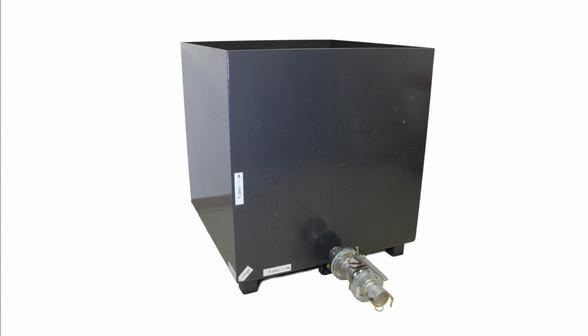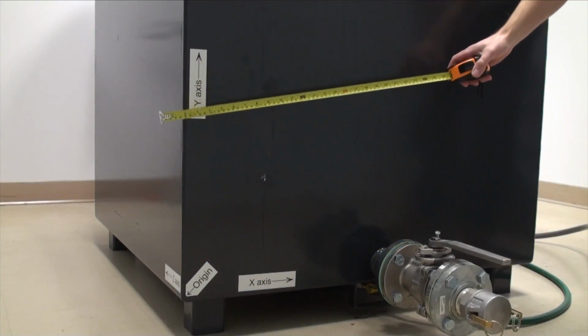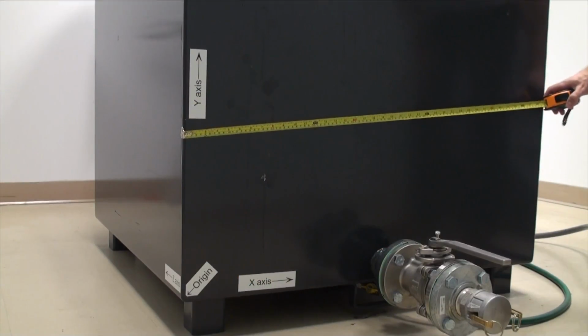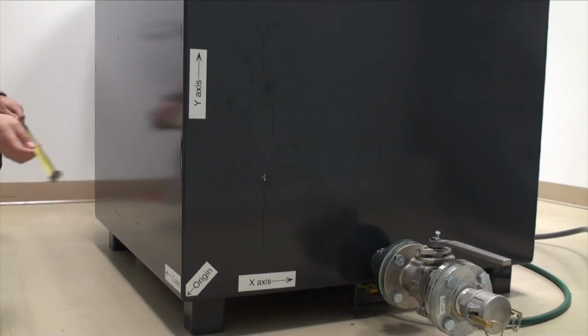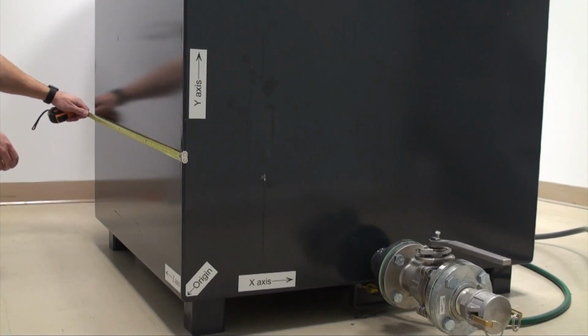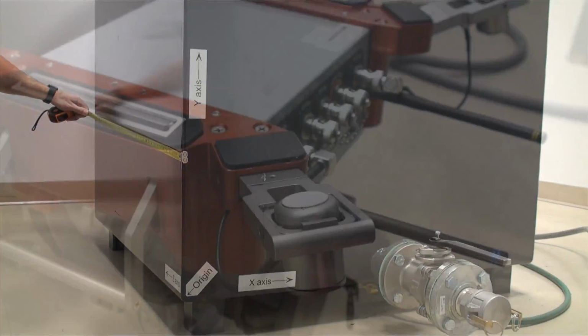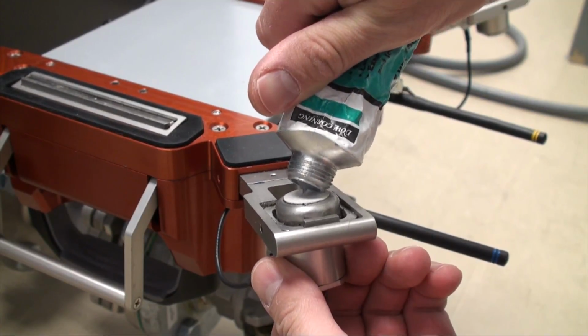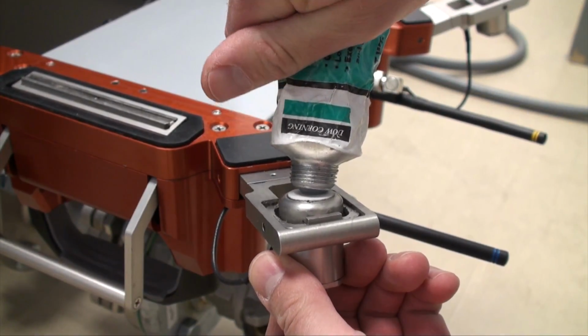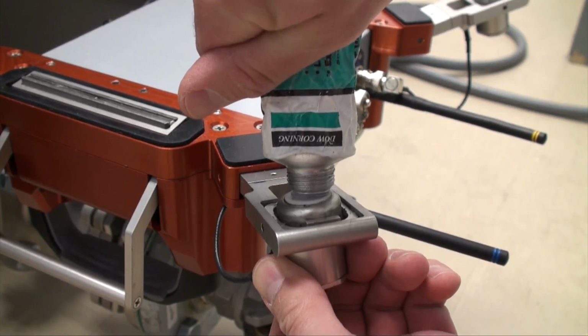For the sake of this video, a demo tank will be used. One of the first steps requires you to identify an origin point on the tank with X, Y, and Z axis. Refer to the transformer schematics or use a measuring tape to get the tank dimensions and keep the values for later. Apply a thin layer of acoustic couplant on all four acoustic sensors.